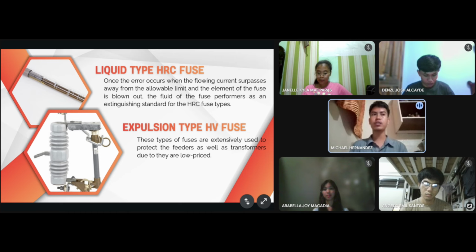When an overcurrent or short circuit occurs, the metal fuse element inside melts due to the excessive heat. As it melts, an electric arc tries to form between the broken ends, but the surrounding liquid immediately cools and quenches the arc. This prevents further damage and ensures that the fault current is interrupted smoothly and safely. In simple terms, the liquid type HRC fuse acts like a smart safety guard for electrical systems. It quickly senses when too much current is flowing and cuts off the circuit before any serious harm can happen to equipment or people.